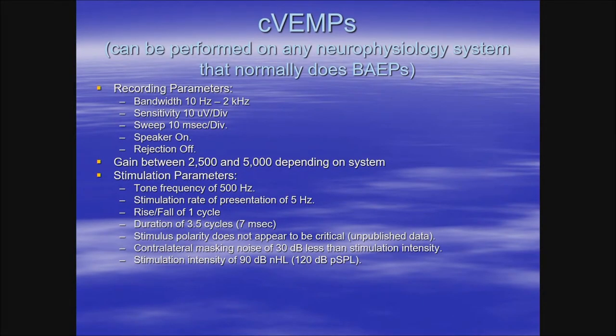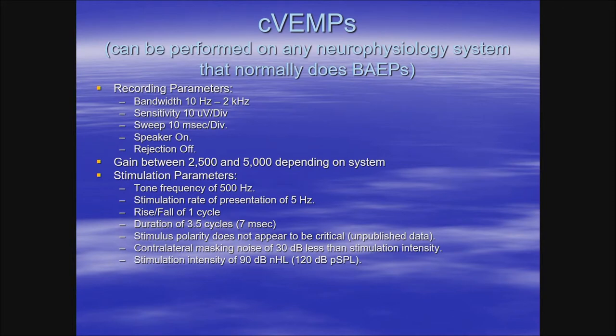These are the parameters for the C-VEMP. If you have a brainstem auditory potential system in your laboratory, you can do VEMPs — both CVEMPs and OVEMPs. You just have to change the sensitivity and gain, and use the right stimulus: the tone and clicks at the intensities I mentioned. If you'd like these parameters, find me afterwards and I can email you the slides or the whole presentation, and I'll be happy to help you set up VEMPs in your laboratory.